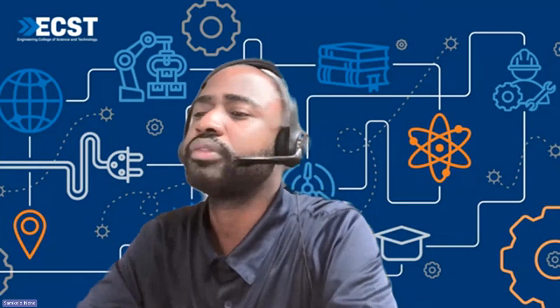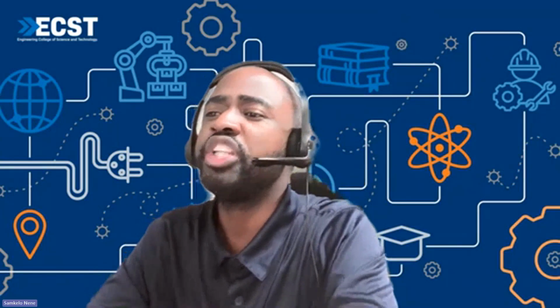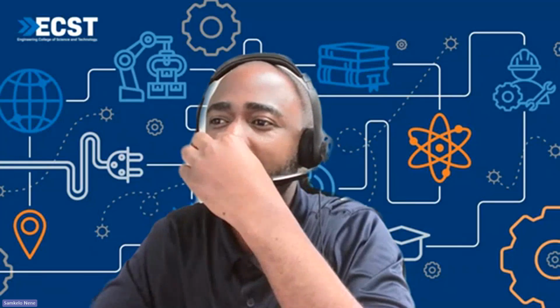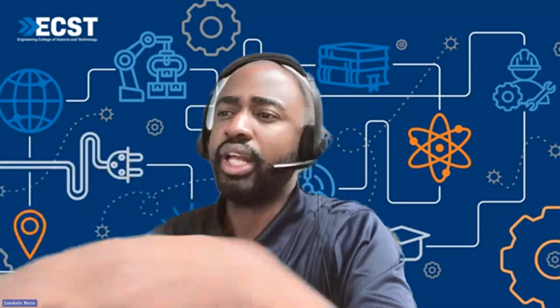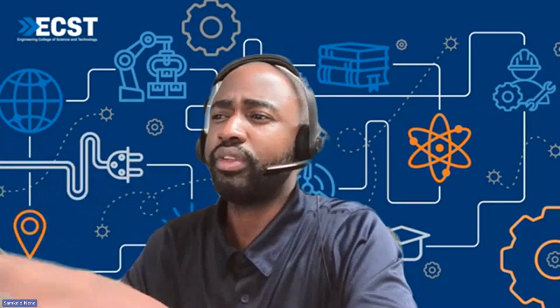So another one is voltage stability issues. If we look at generators, they use excitation systems, which supply DC currents to the field windings, which then leads to the magnetic field that helps produce the electricity. So that's one of the functions of the excitation system. Also, this excitation system helps with providing the reactive power.